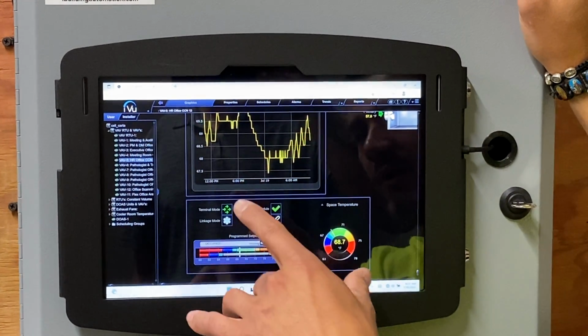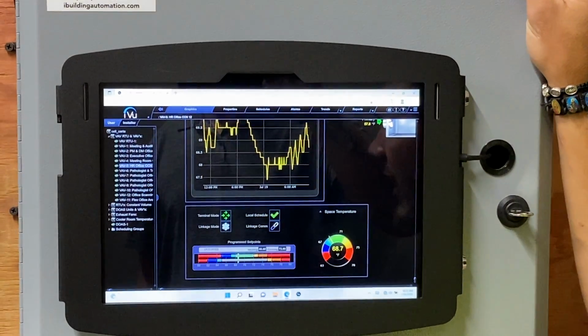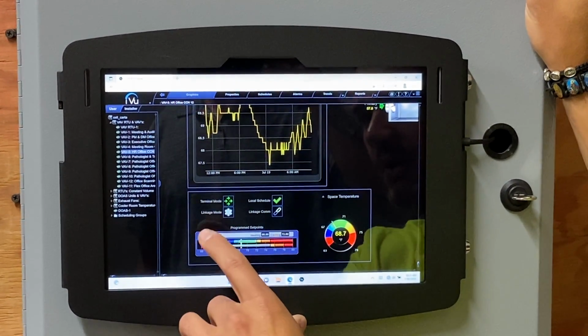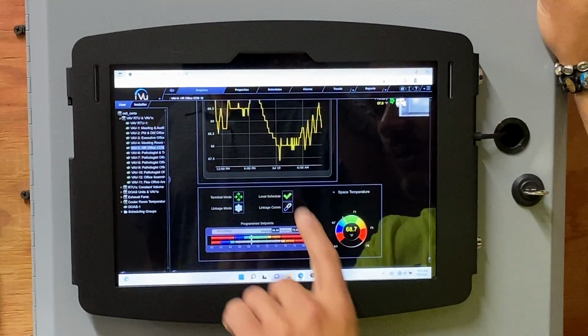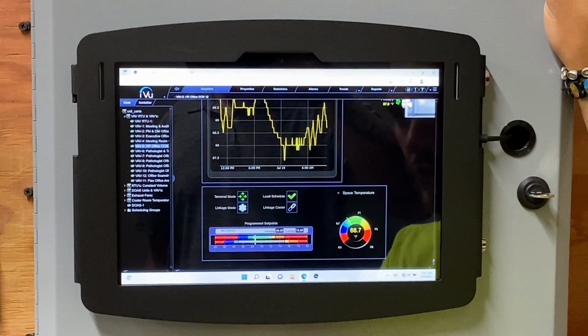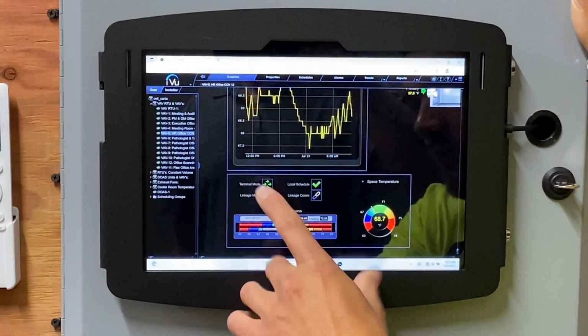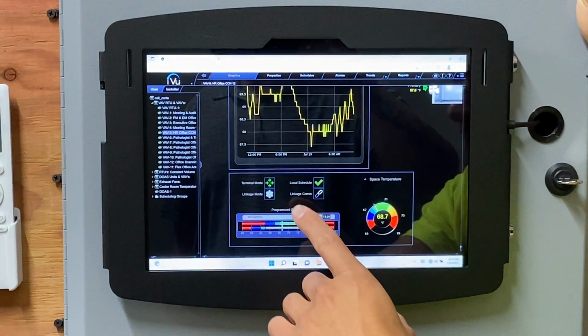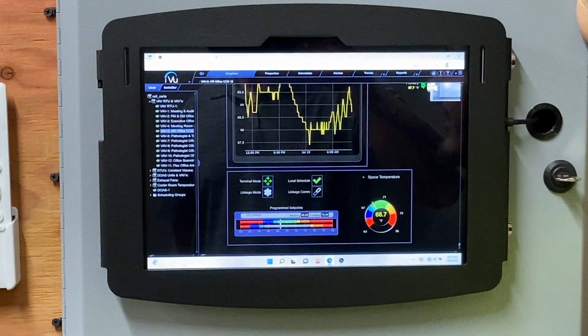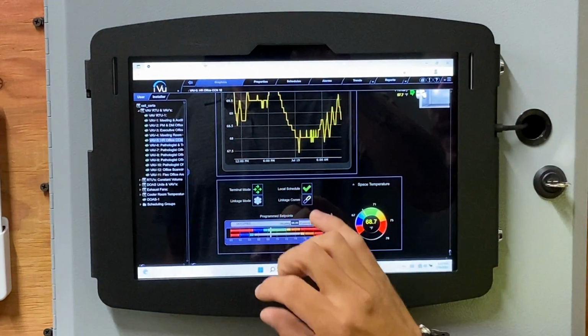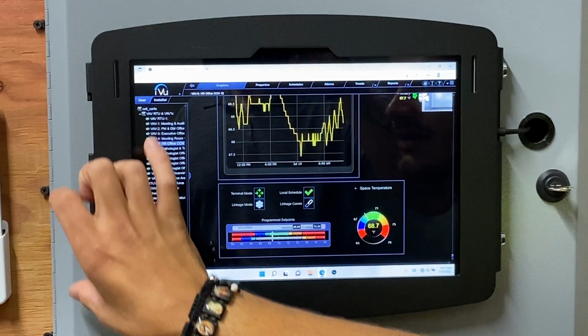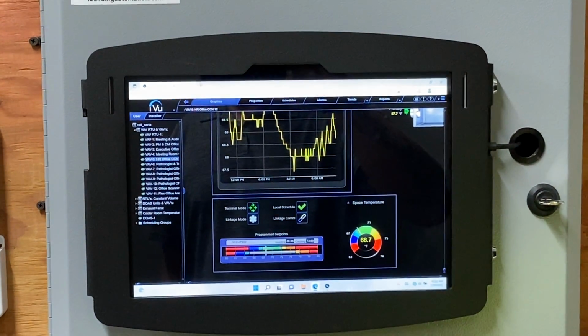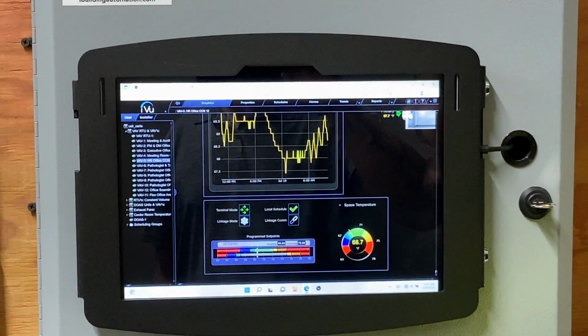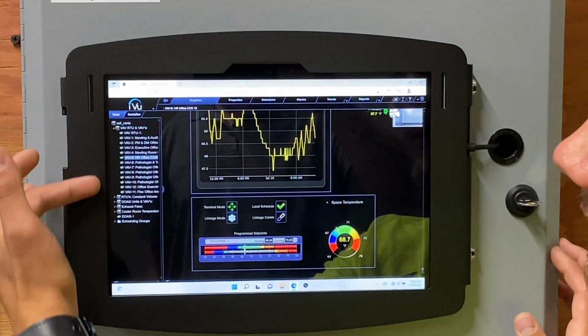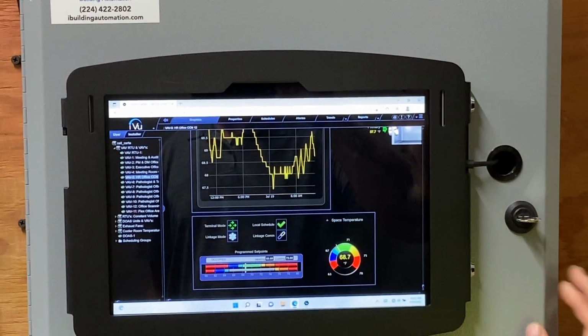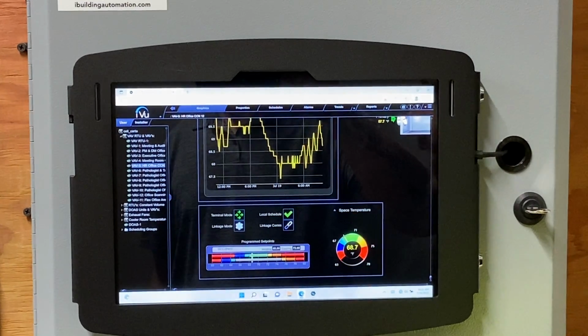Inside of this, you have your four boxes, which again is a troubleshooting term I'm going to reference. You have terminal mode, linkage mode, local schedule, and linkage com. Now this is new — they went away from words, so for linkage mode we have a snowflake, meaning we're in cooling mode, and our terminal mode has these arrows, which indicate that we have a fan on at the rooftop unit. Now the linkage communication is between these VAVs and that rooftop — that's not the network that we have to everything. The network we have just allows everything to communicate back to this device. But these 11 VAVs are linked to that one rooftop unit, which is serving that other space, so nothing else is going to come into accordance with them.